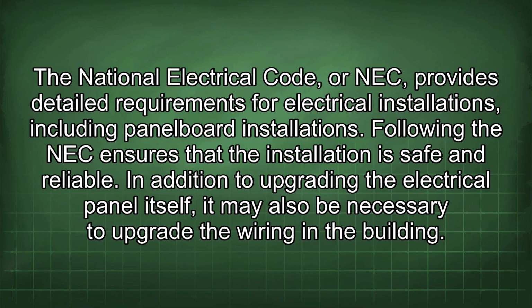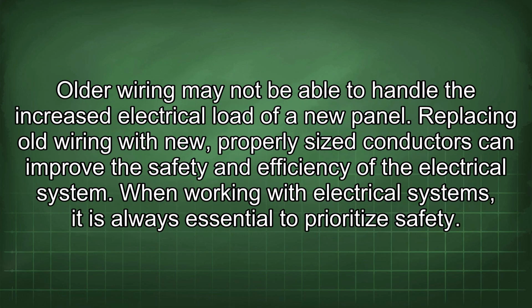In addition to upgrading the electrical panel itself, it may also be necessary to upgrade the wiring in the building. Older wiring may not be able to handle the increased electrical load of a new panel. Replacing old wiring with new, properly sized conductors can improve the safety and efficiency of the electrical system.